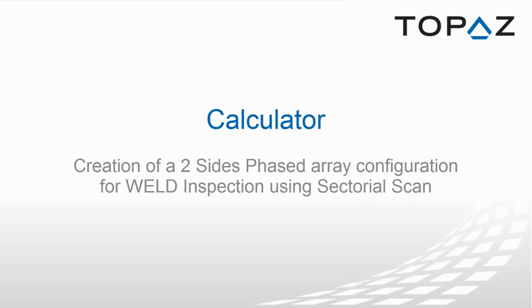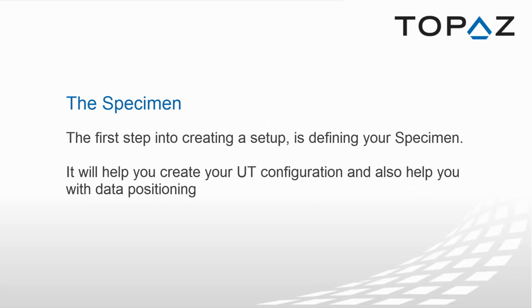Calculator. Creation of a 2 sides PA weld inspection using sectorial scan. The specimen. The first step into creating a setup is defining your specimen. It will help you create your UT configuration and also help you with data positioning.